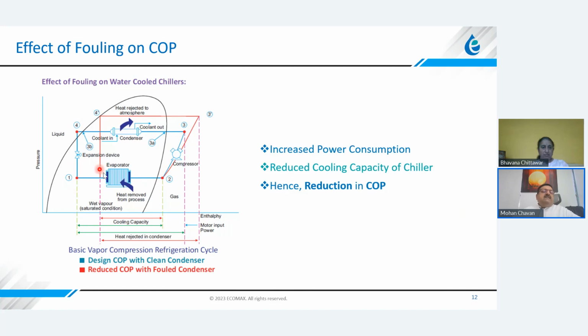Now, as there is scaling inside the tubes, you will find that the discharge pressure is increasing from 3 to 3 dash. The moment there is fouling, you will find that this curve has shifted from 2 to 3 to 2 to 3 dash, and when you project this line on the pressure enthalpy curve, it will hit at 4 dash. In the previous case, when the condenser was clean or new, your cooling capacity was this, right here. So it is larger. The moment there is fouling inside the tubes of the condenser, your cooling capacity has dropped to this red line, right?